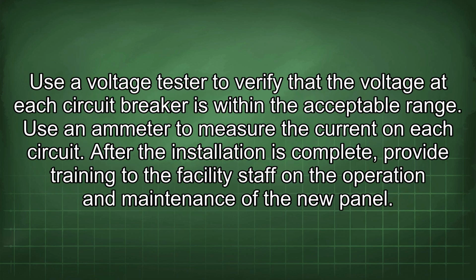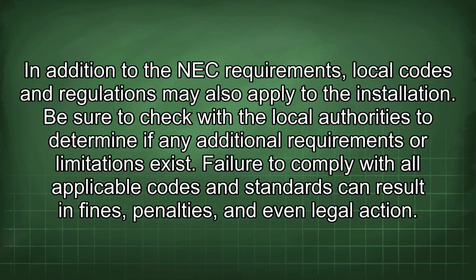Use a voltage tester to verify that the voltage at each circuit breaker is within the acceptable range. Use an ammeter to measure the current on each circuit. After the installation is complete, provide training to the facility staff on the operation and maintenance of the new panel. In addition to the NEC requirements, local codes and regulations may also apply to the installation. Be sure to check with the local authorities to determine if any additional requirements or limitations exist.